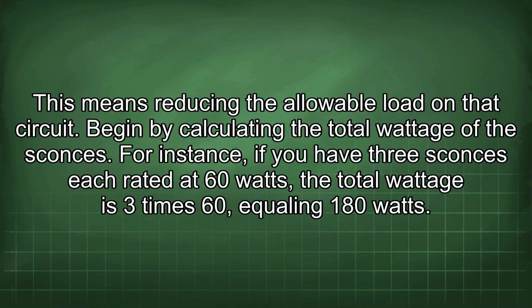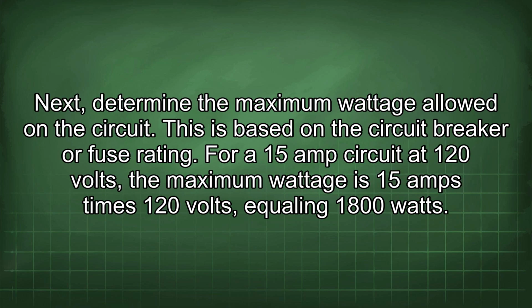This means reducing the allowable load on that circuit. Begin by calculating the total wattage of the sconces. For instance, if you have 3 sconces each rated at 60 watts, the total wattage is 3 times 60, equaling 180 watts. Next, determine the maximum wattage allowed in the circuit. This is based on the circuit breaker or fuse rating. For a 15 amp circuit at 120 volts, the maximum wattage is 15 amps times 120 volts, equaling 1800 watts.